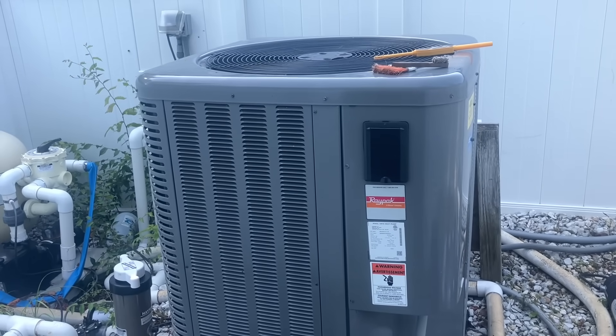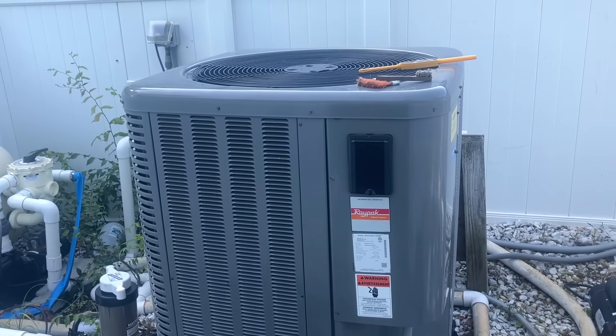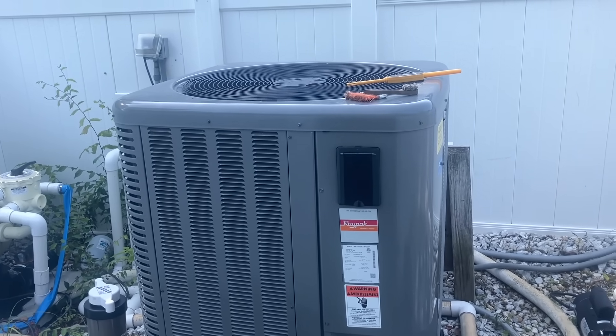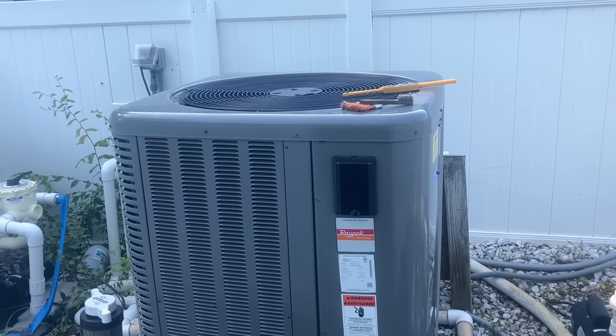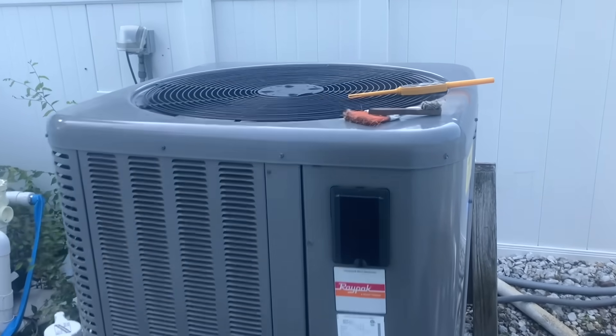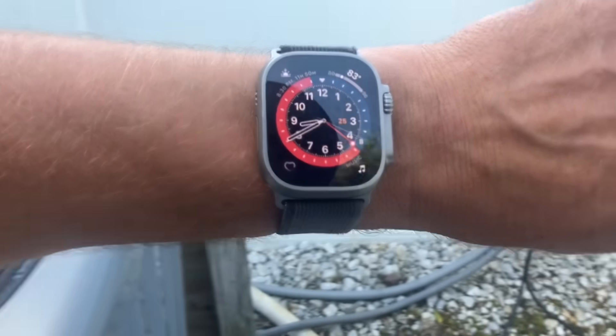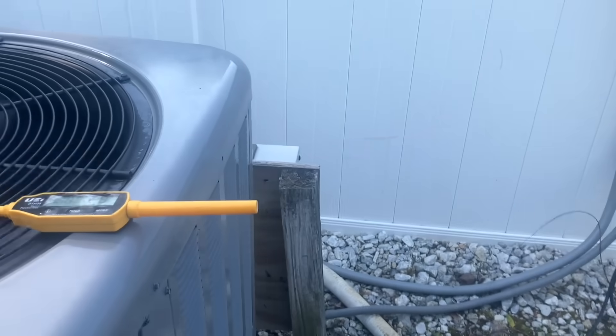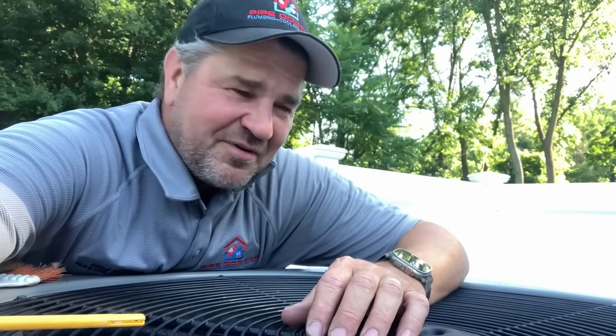After brushing off the coil and letting everything settle down, our low side pressure is 157, high side is 377. Pool temperature is 87 degrees, outlet temperature is 91. My ambient discharge is 71 degrees and my outdoor ambient is 68 degrees.